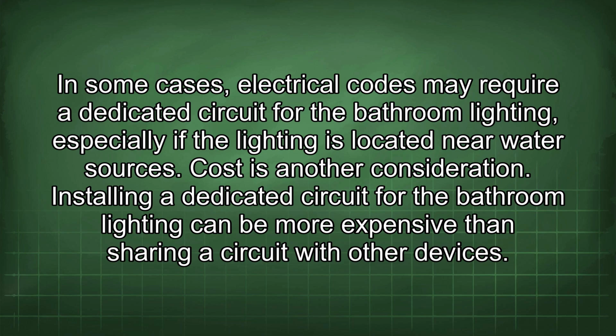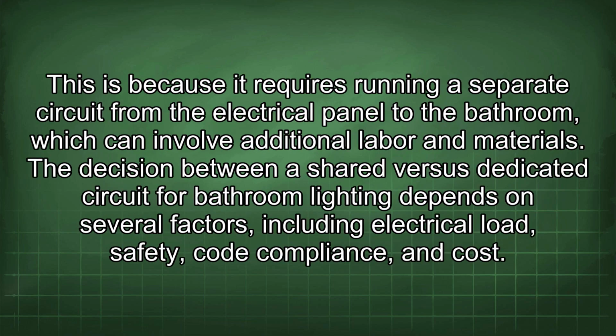Installing a dedicated circuit for the bathroom lighting can be more expensive than sharing a circuit with other devices. This is because it requires running a separate circuit from the electrical panel to the bathroom, which can involve additional labor and materials. The decision between a shared versus dedicated circuit for bathroom lighting depends on several factors, including electrical load, safety, code compliance, and cost.